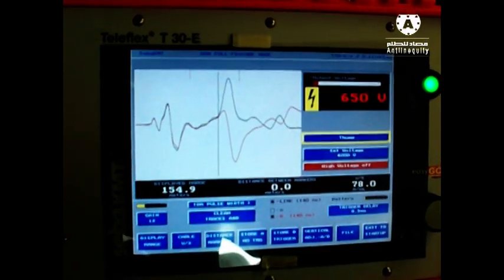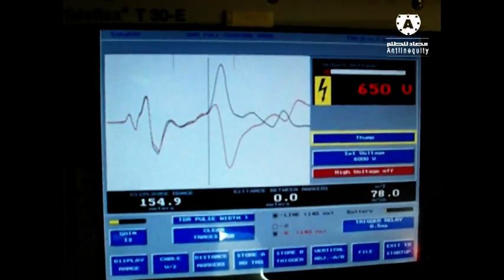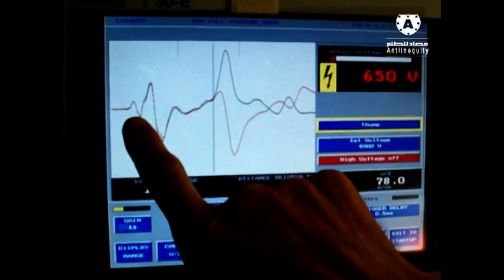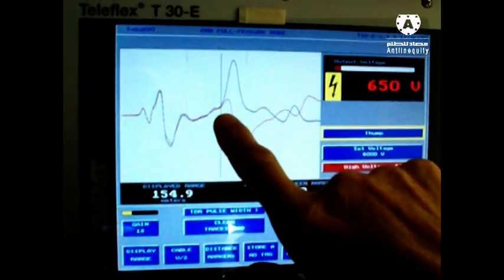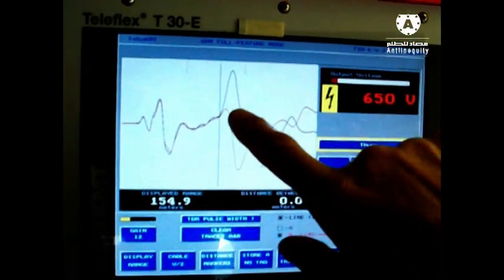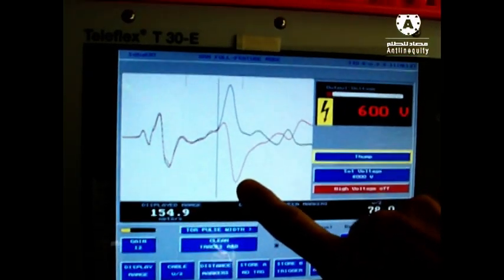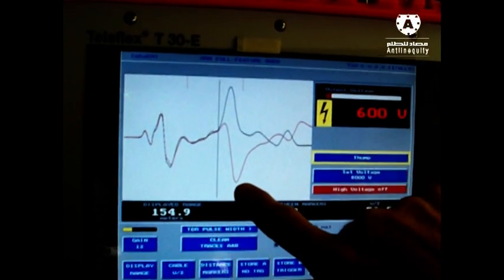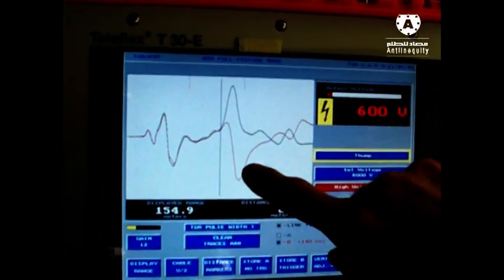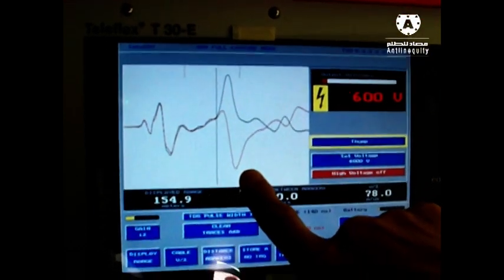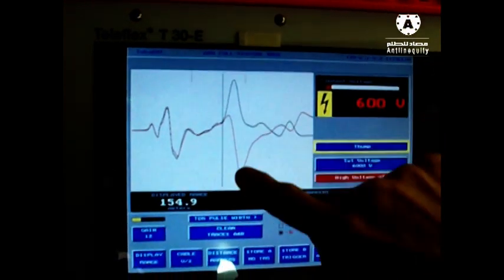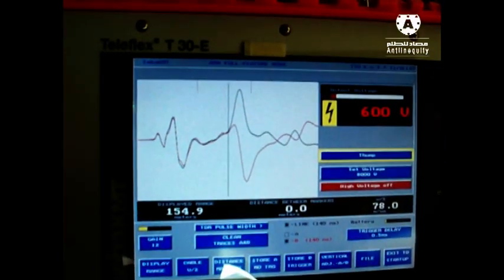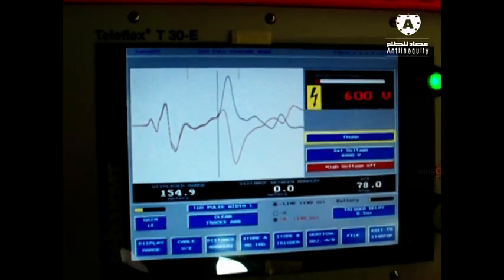Now we get a very nice picture, and what we see here is the beginning of our TDR. The impulse is moving, nothing is different to the healthy picture, but at the end we get a flashover. We create a 0 ohm resistance fault by a flashover by the high voltage, and a 0 ohm resistance means in TDR measurings that the curve goes down to zero, to minus. And we're divided into two curves. This is our point where our cable fault is.